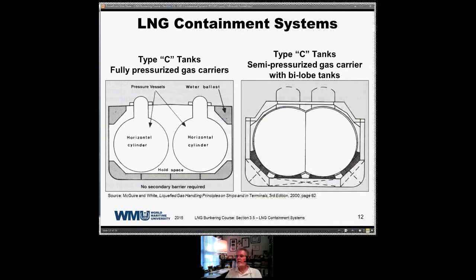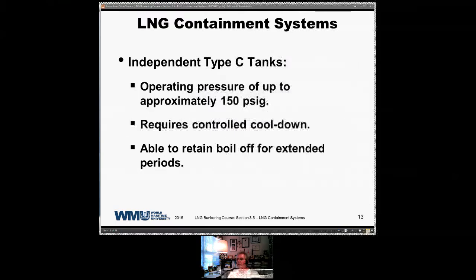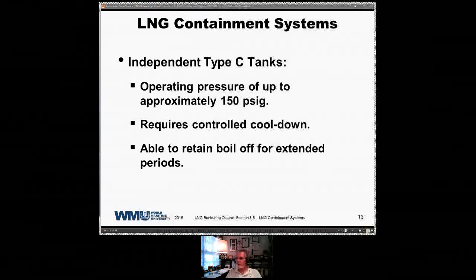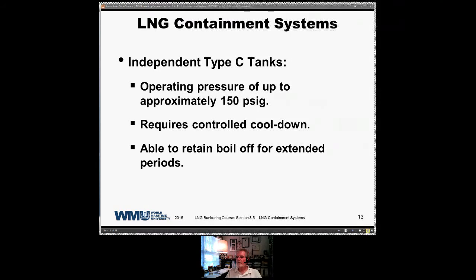Independent Type C tanks have operating pressures up to approximately 10 bar, 150 psig. So these are the ones that you can do a pressure transfer of liquid from the Type C tank to wherever it's going, to the receiver. They do require a controlled cool down, though, because you're talking a very robust material. You're talking about a thickness of steel, and you just cannot introduce LNG into a tank of this nature.